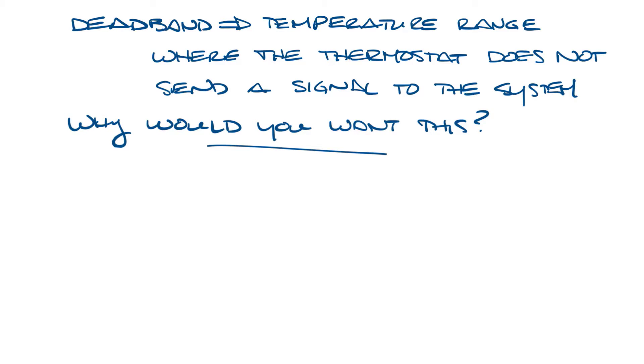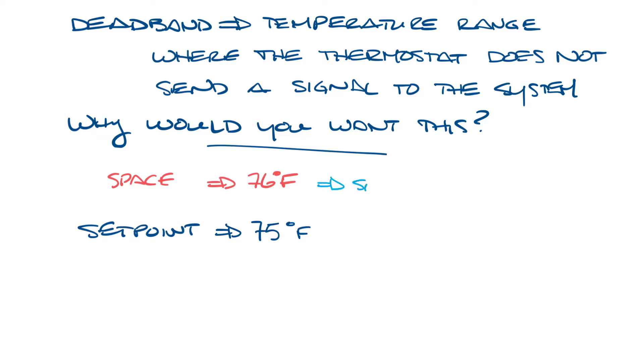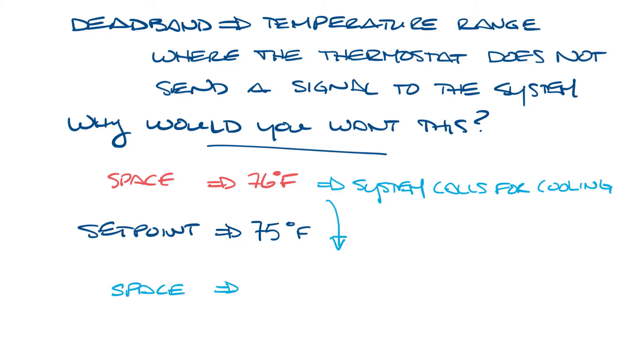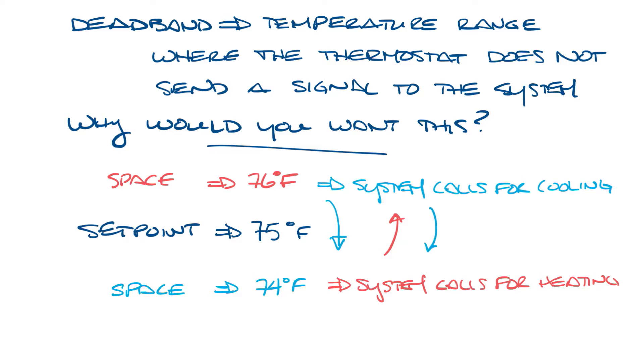Let's say that you have an HVAC system that has heating, cooling, changeover, and your thermostat set point is 75 degrees. If your space is 76 degrees, the thermostat will call for cooling to get the space back to 75 degrees, so the cooling goes on and it starts cooling the space. Let's say the system cools the space down to 74 degrees. Since the set point is 75 degrees, now the thermostat will call for heat. And then when it gets to 76 degrees, it's going to call for cooling again, back down to 74, call for heating — and it will go back and forth like this. You really don't want your system working like this. You don't want it switching between heating and cooling all day.